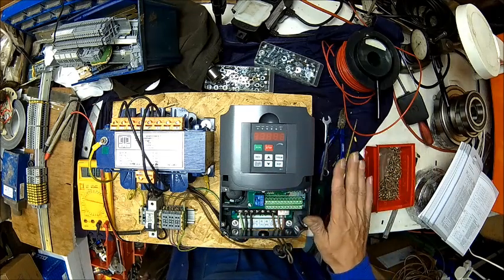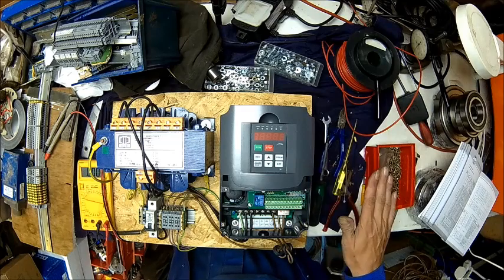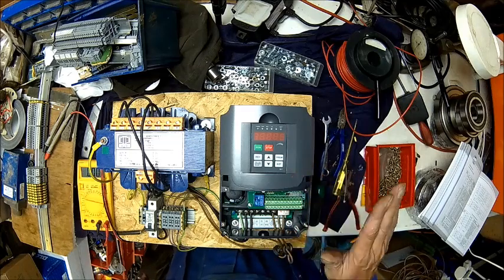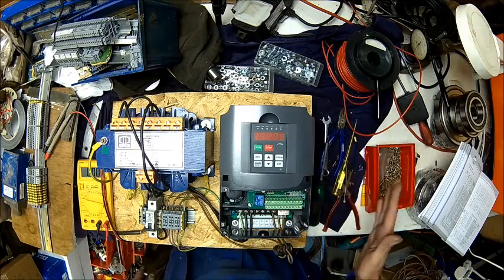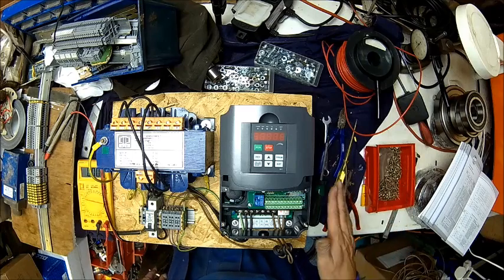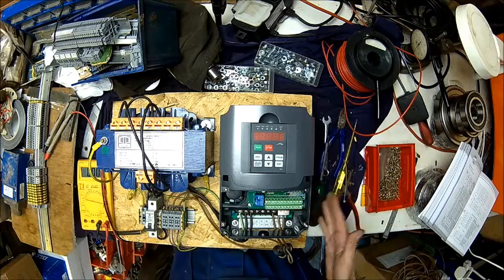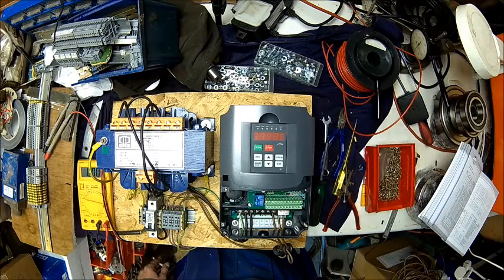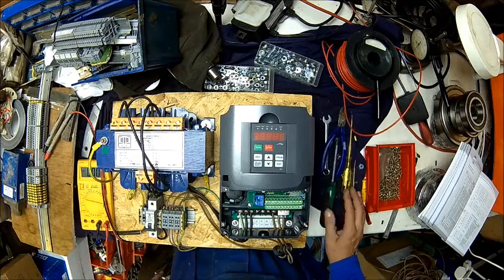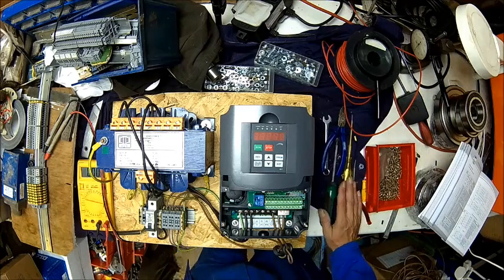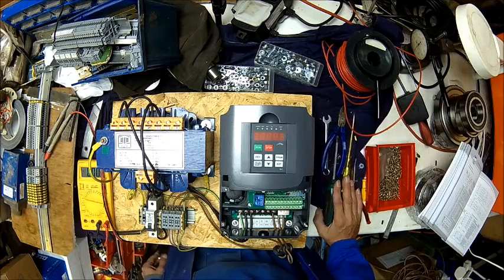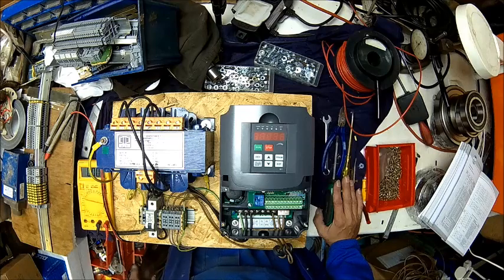I know someone will talk about power factor. Well, we'll leave that alone for now. Power is actually voltage times current, and at a lower voltage you need more current for the same power. That's the reason why the 230 volt has a higher current capacity, but the problem is if you got a 400 volt motor, you need 400 volts.